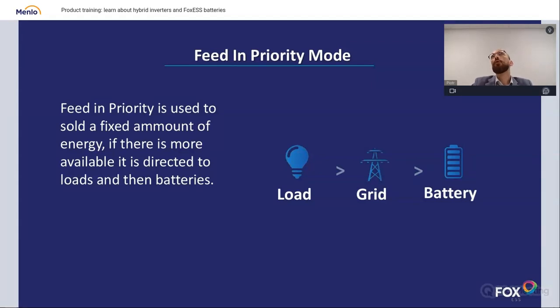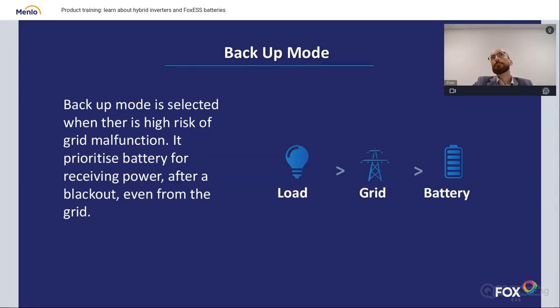This is good for some clients having contracts with their distributors. If they have some really nice rates, it can be set that way to sell energy. In the backup mode, the unit will be like a prepper. It will prepare itself for a blackout. It will charge the battery to a given limit, to a given SOC, and will always try to have some set energy to be provided during the blackout.